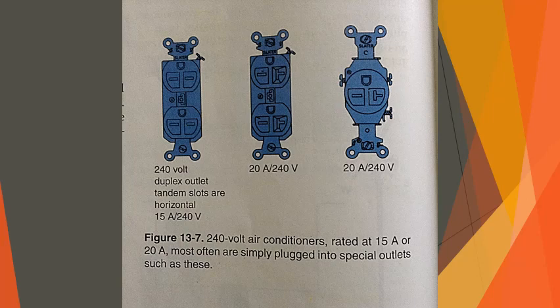Other air conditioners which operate on 120 volts can be plugged into any regular duplex receptacle outlet. Air conditioners can often be connected to the same circuit as heating units, since they would not be operating at the same time. In these situations, only the larger load is considered, as explained in the section on non-coincident loads from the previous chapter.